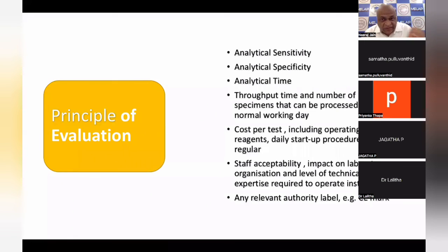Specificity means it is measuring that analyte only, nothing else. You must have seen in many three-part differentials, they measure on the basis of size, and nucleated RBCs are counted as lymphocytes. So that analyzer is not specific for total leukocyte count. We have to correct. So that is specificity. Analytical time is how much time it will take to complete one cycle. Suppose it is taking 2 minutes, that doesn't mean in 60 minutes you will be able to test 30 samples, or in 2 hours you will be able to test 60 samples. In between, the machine may need some rest. The machine may need some washing cycle. So how many samples you are able to process in your working hours, maybe 4 hours or 3 hours, that you have to see.